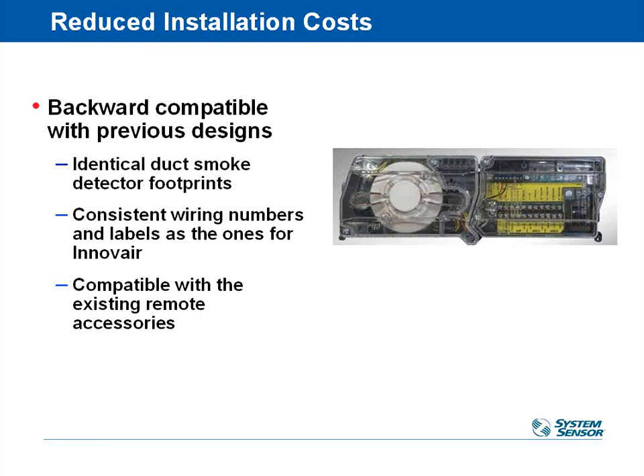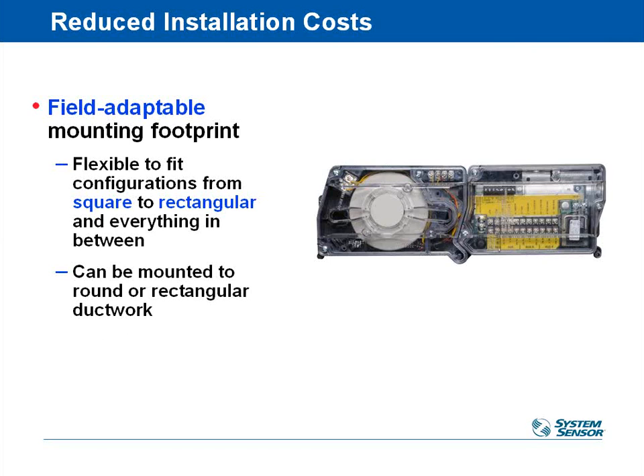These are backward compatible with the old Innovair line in terms of the accessories and in terms of how the terminations are labeled. So all the wiring terminals, 1, 2, 3, 4, 5, and so on down the line, are labeled the same way on the old product and the new product. So if you're replacing one, it should be very easy to swap out. And then most of the accessories are compatible as well. The one thing that is not compatible is the sampling tubes. You would have to replace the sampling tube.